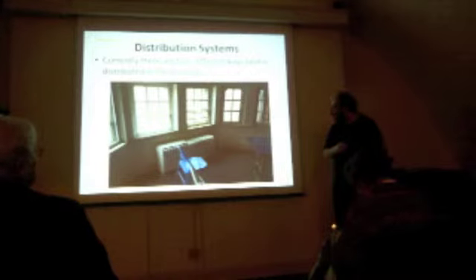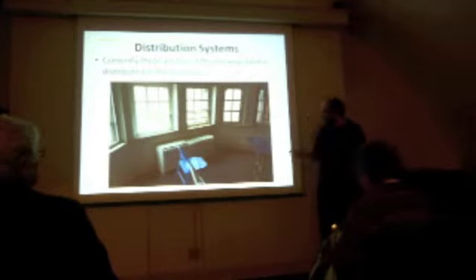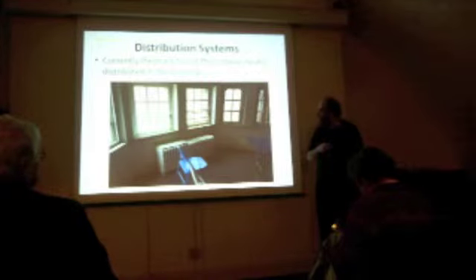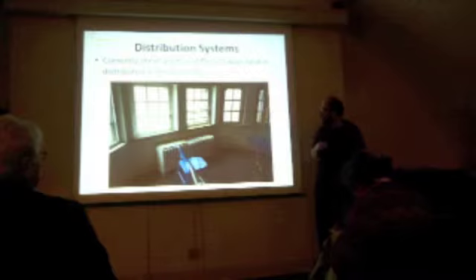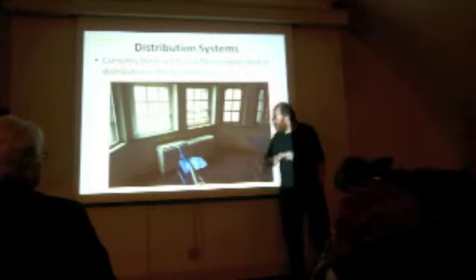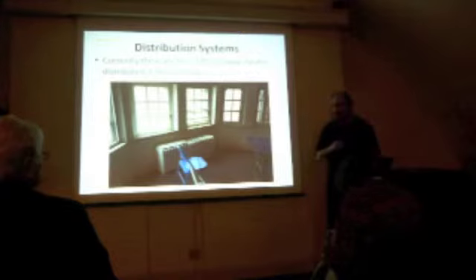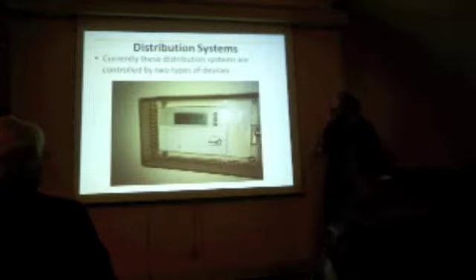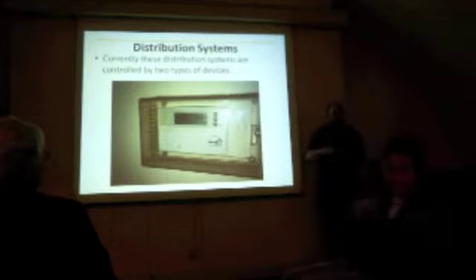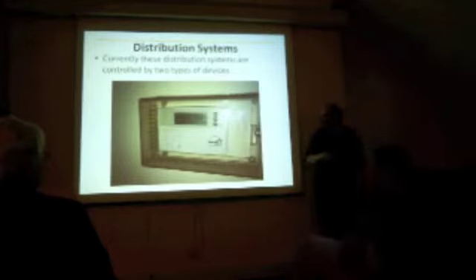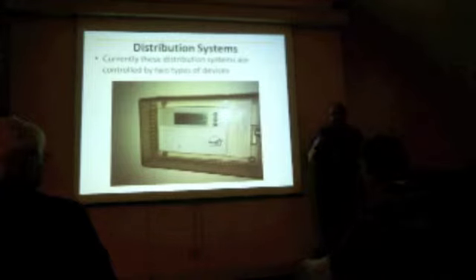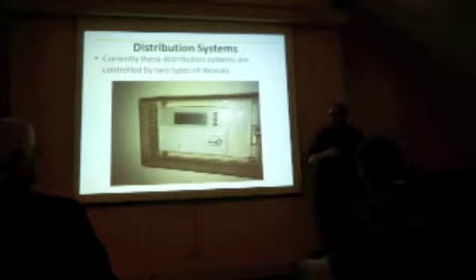You have at least one space that we found with the old-fashioned radiators, and so this was in the little classroom that's right down around the corner here. These radiators are only in that space, at least as far as we could tell. So all of the bits of distribution are controlled by one of two different control technologies. All of the ones that are the hot water systems, all of the ones that have either the baseboard or the blower system like the sanctuary, are controlled off of thermostats. And these allow you to control day-night cycles to be able to set them down at night and ramp them back up in the day.